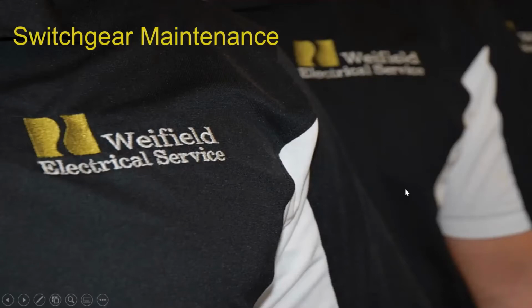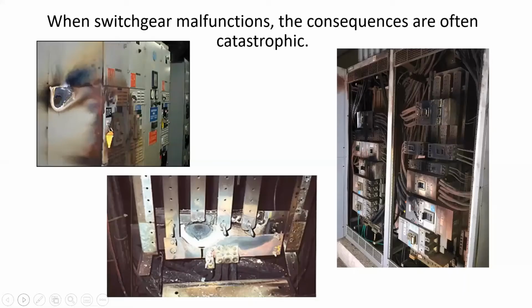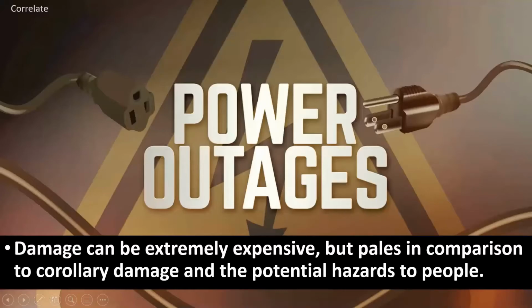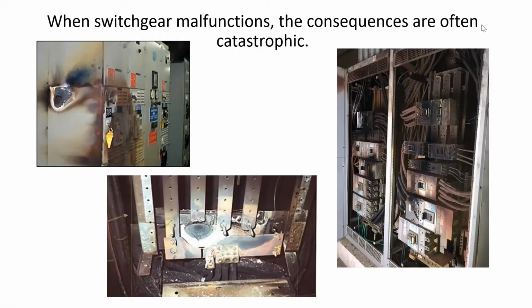I think this space bar—there we go. Okay, obviously when a switchgear malfunctions it's usually a catastrophic failure, right? Actually, a lot of the failures you'll see are a slow burn where you have a termination—because terminations are where all electrical fails. It's the biggest point of failure, and it's overheating, overheating for years and years, and that's probably more common than an actual catastrophic failure. Go ahead.